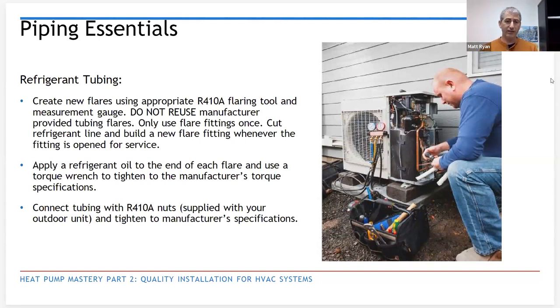Refrigerant oil to the end of the flare, we don't do that. We actually use a product called Nylog. We just went to a recent training class, and they were actually back to not using anything. So that's changed over the years. I'd say consult your manufacturer; if they have brand specific training or tech support, check with them.